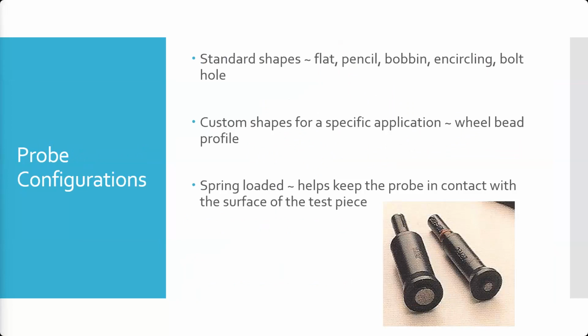And the probes shown here are actually spring-loaded. It's a flat face. You're going to use some of these, this style right here on the right with the slightly smaller. You can see they've just got 2 different size coils inside of them, that help to keep the probe in contact. Remember I said very small movements of the probe in relation to the surface can cause false indications on your display. And so by having a spring-loaded probe like this with a real wide base, it helps to keep it nice and solid on there.